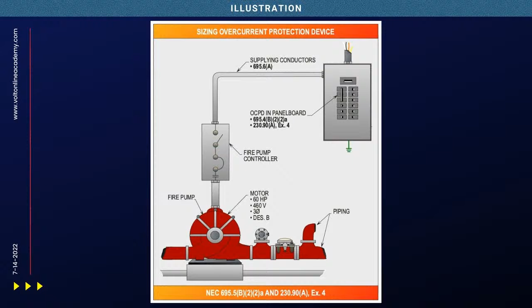But when I go look at 695.4(B)(2)(a), it's going to tell you that I'm going to take that at 600%. Okay. Oh, wow. Yeah. Okay. So when you do this calculation for that overcurrent protection device, if you look, there's a note up there where it used to be in previous editions, and we tell you the 600% times the full load amperage. That fire pump was in the 1996 NEC and previous editions of NFPA 20.